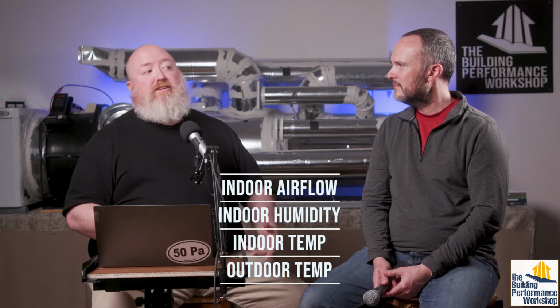All of those things change how many BTUs that system performs at, every one of them. That's why Manual J can't give you a quote-unquote tonnage—number one, there's no such thing as a ton, and number two, you change the conditions, you change the performance. A system doesn't give me the same number of BTUs. It's not a magic box, it's not a refrigerator. It doesn't go in everybody's house and sit at the same temperature and do the same thing. Part of it's outside, part's inside, there's ductwork somewhere—it might be in the attic, might be in the basement. A system in Boston gives me a lot more BTUs than a system in Phoenix.